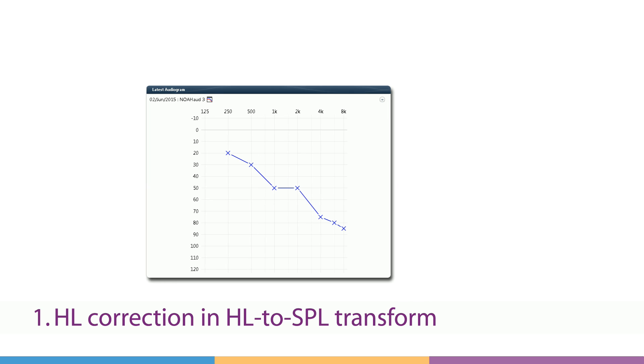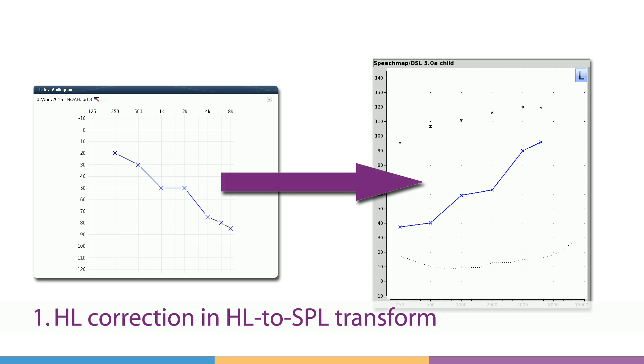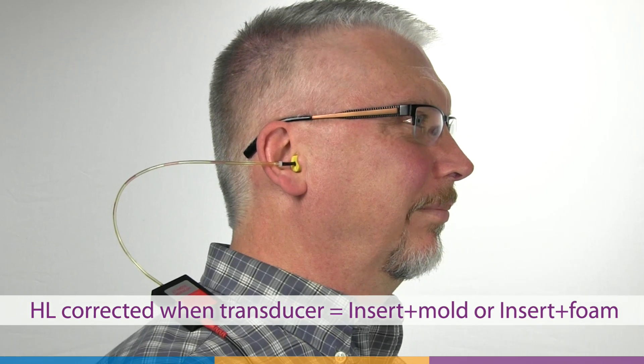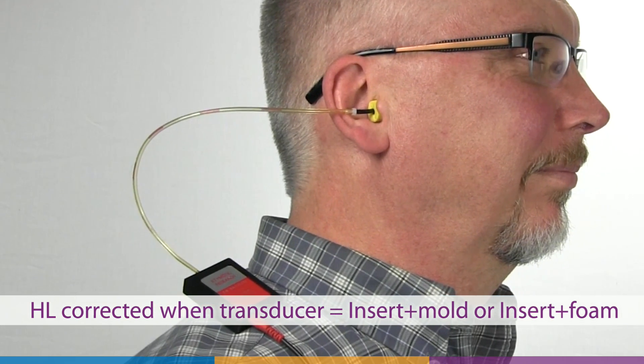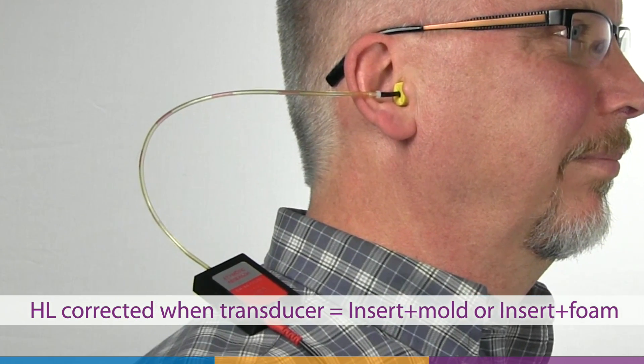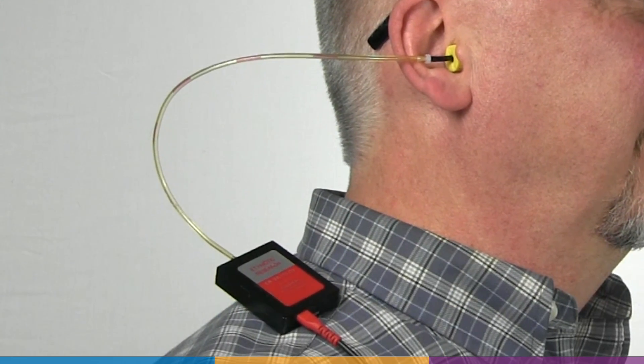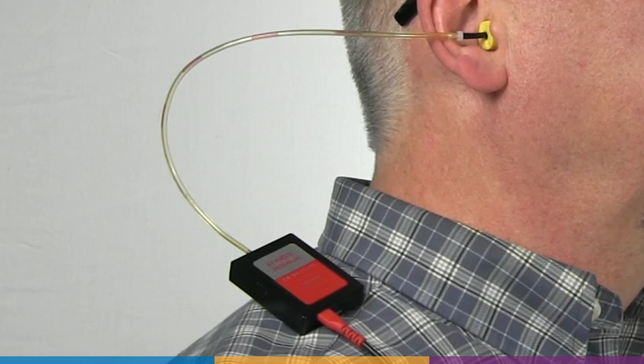One: to correct and convert HL thresholds to the SPL format used by many fitting methods and real ear approaches. Audiometers are calibrated to an average adult ear canal. Any differences in volume and impedance will be reflected in the measured hearing levels. Using a measured RECD ensures that the SPL thresholds accurately capture the true level of hearing sensitivity for the patient in question.